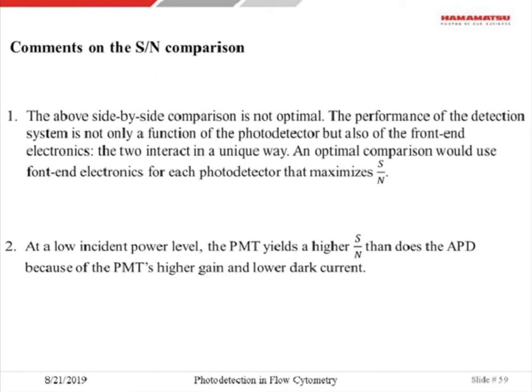Can APD do as well as PMT? The answer is yes, it can. But because APD has much lower gain, you need electronics with very, very low noise. If electronics has no noise, then gain doesn't matter anymore, and the higher spectral sensitivity of APD would make it a better photodetector. So it's not just the photodetector—electronics plays a critical role.